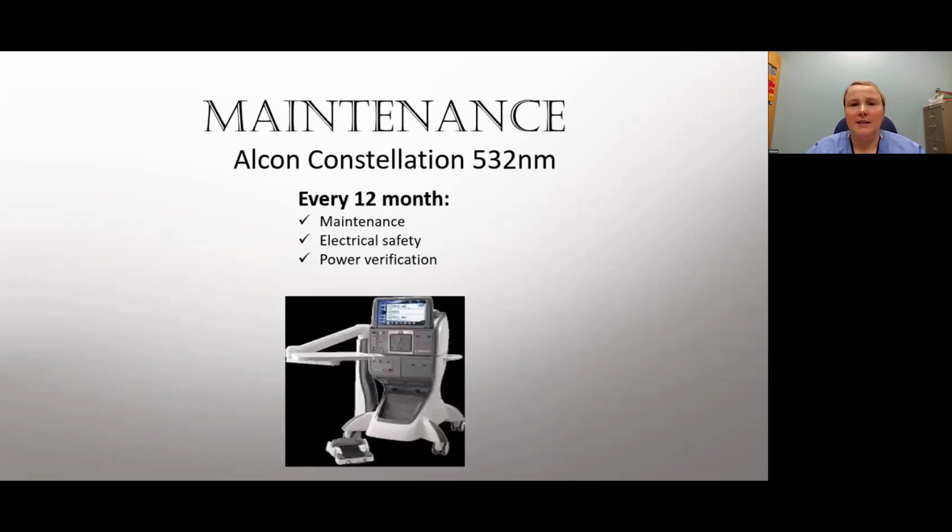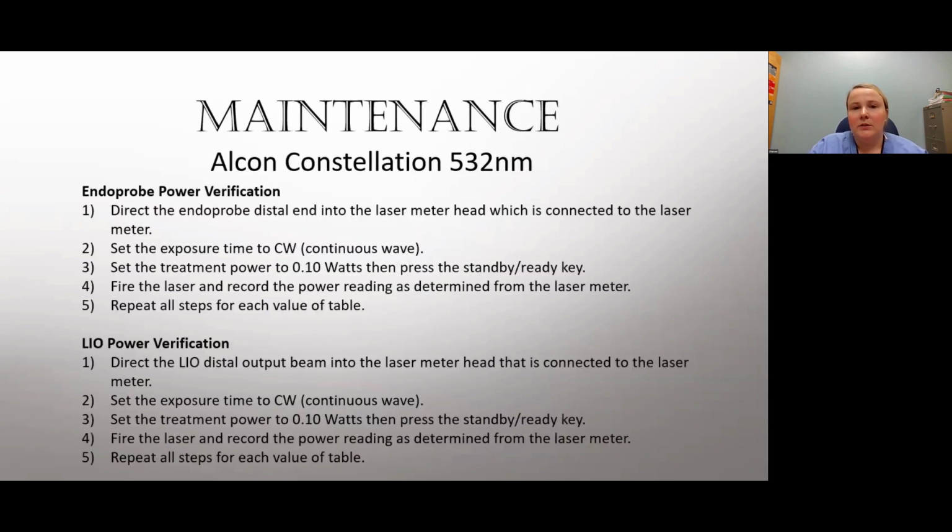So the Alcon Constellation, the 532, for what the manufacturer recommends is every 12 months. So you want to do maintenance, electrical safety, and power verification. So for the maintenance, this laser has an Endo Probe and LIO.